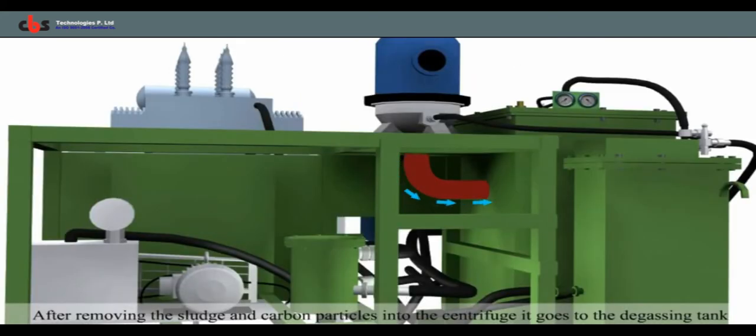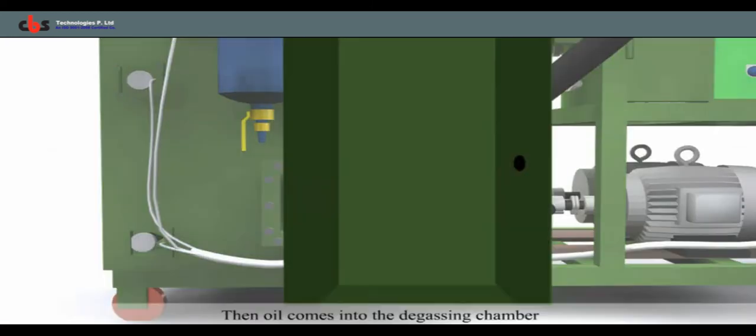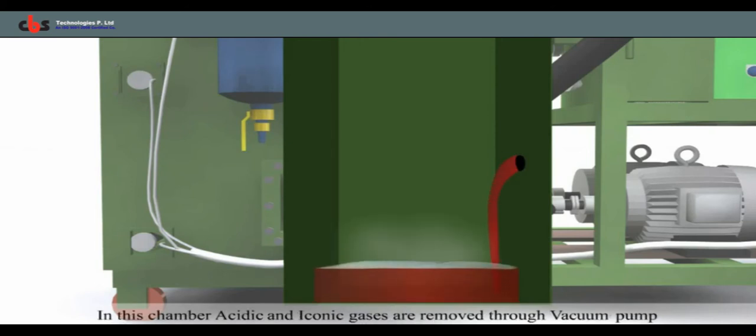After removing the sludge and carbon particles in the centrifuge, it goes to the degassing tank. In degassing chamber, emulsified water and acidic and ionic gases are removed through vacuum pump.